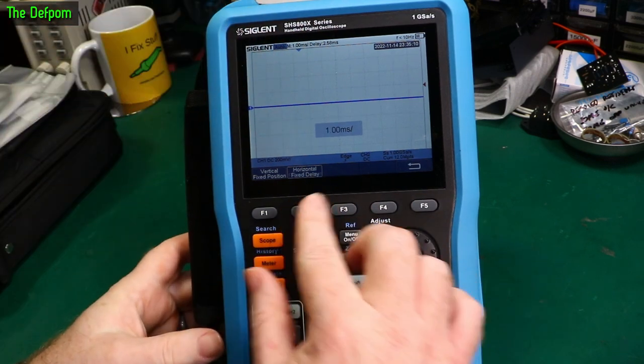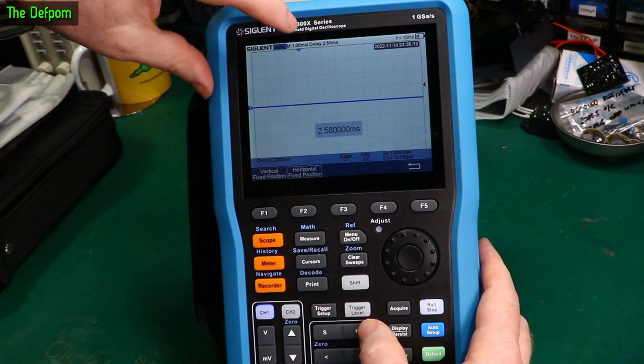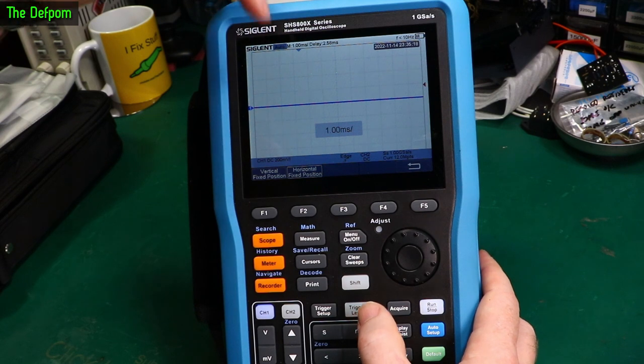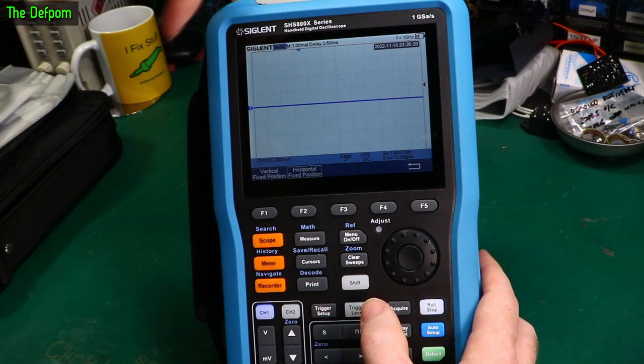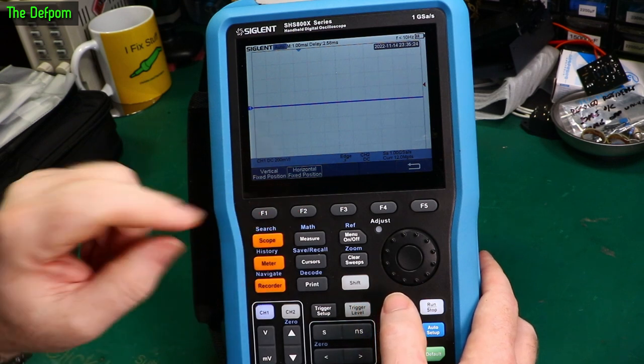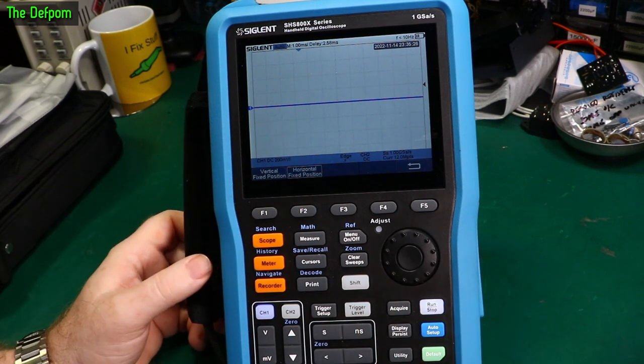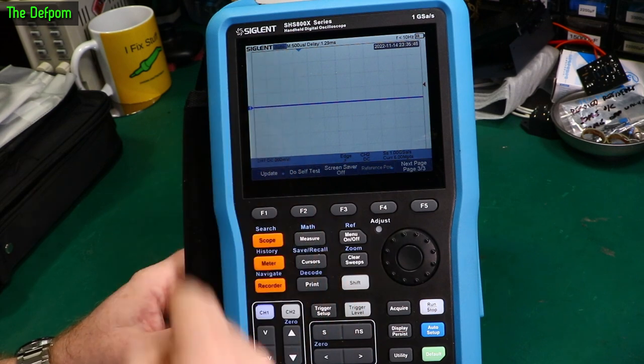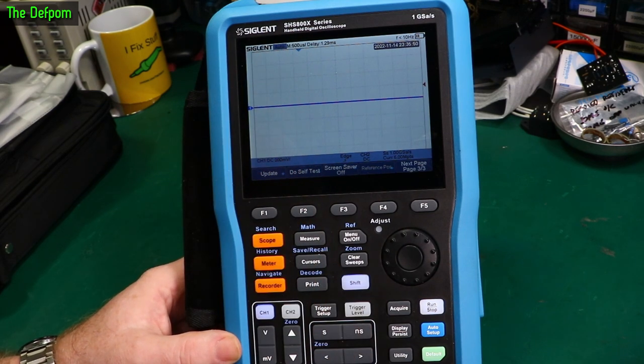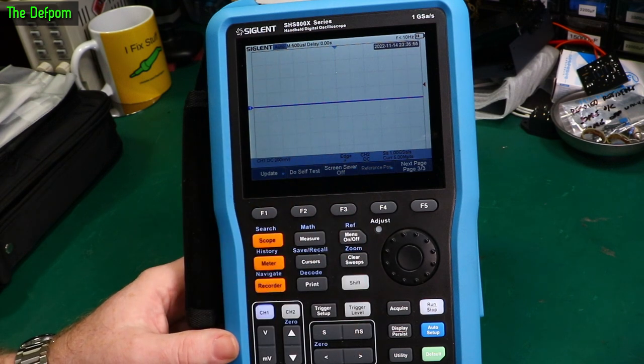And then as you zoom in and out, you see the thing is moving as well. So it's always in the same position there. But this is shifting with it. If you change to the other type, as you shift in and out, that stays exactly the same place. So if you get an issue where you find the trigger point is always moving around on the unit but it's annoying, change to the other type. The oscilloscopes have this feature as well. If you have to find it. And if I wanted to recenter that, what I should be able to do is do shift and zero. There we go. That's centered. Easy enough.